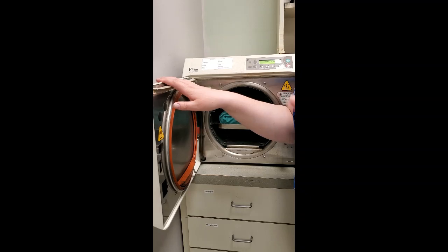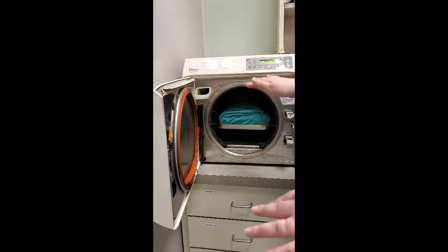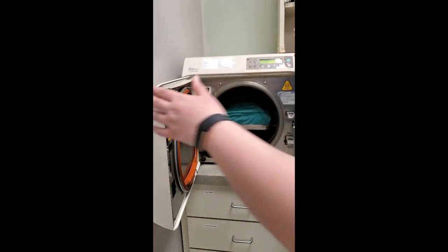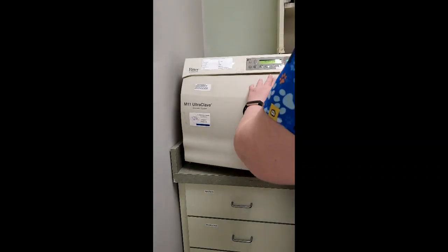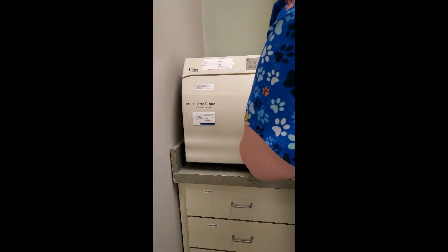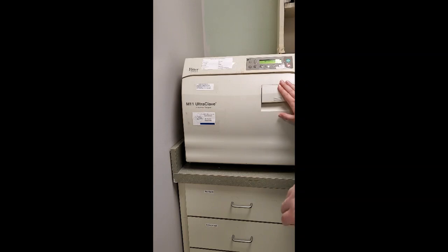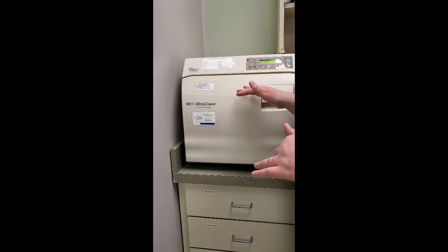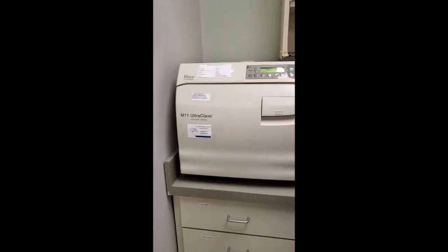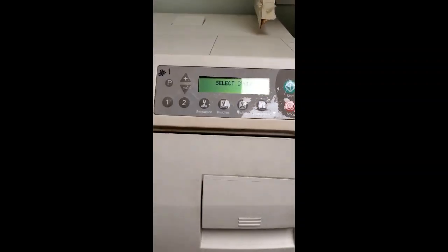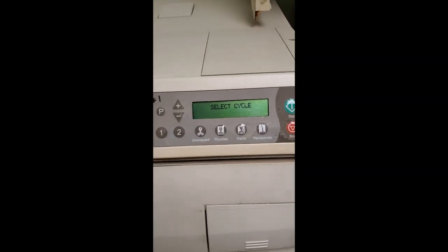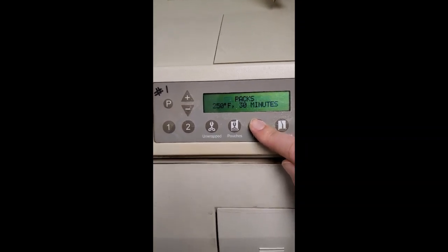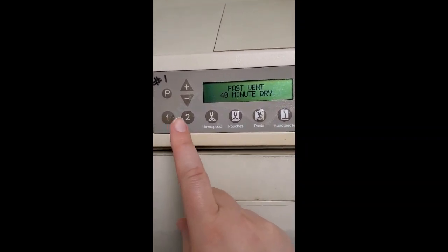Here we don't have to set any time, temperature, or pressure. It's an automatic cycle, which I'll show you when we set that in just a second. So you're just going to close the door. So for this autoclave, we're going to run our packs at 250 degrees. They're going to be running for 30 minutes, and the PSI is going to be between 15 and 16. So right here, what you're going to do is just select packs, and you can see 250, 30 minutes.